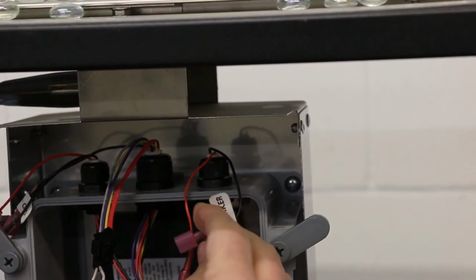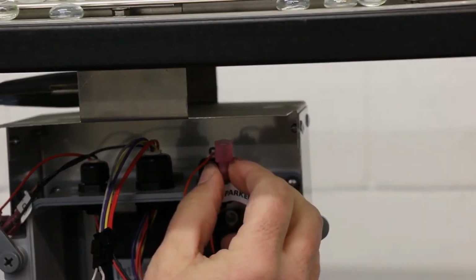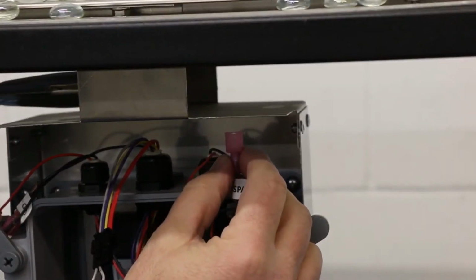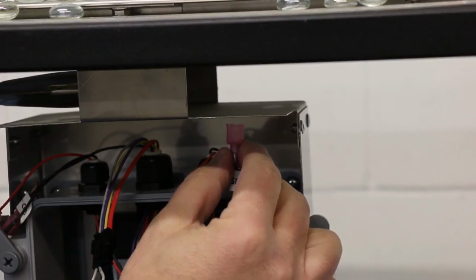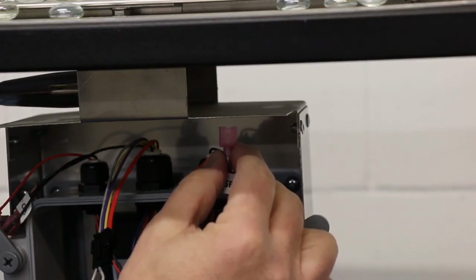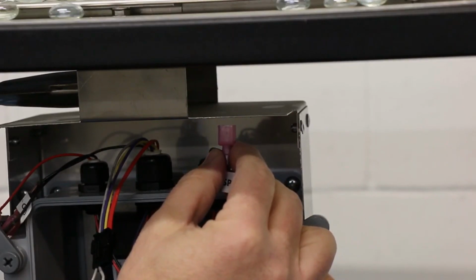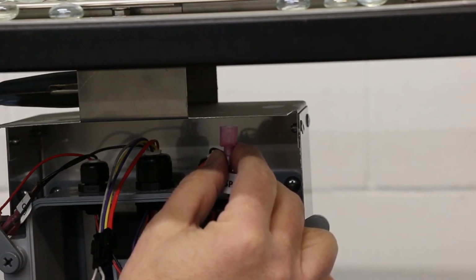If you do not have a voltmeter, you can also validate the module and a portion of the wire harness by disconnecting the sparker spades and holding the sparker wire connection coming from the module close to a metal surface as shown here. If you see the spark, you know your module is fine and the lead coming off the module is fine, and the only items left are the lead to the electrode or the electrode itself.